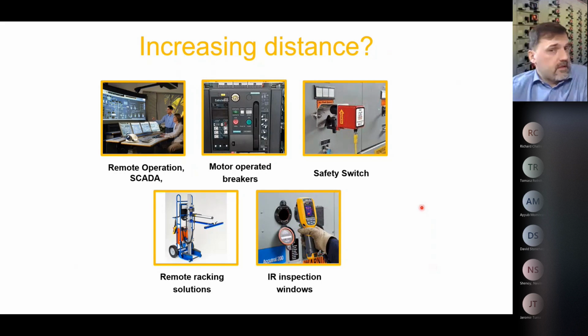We might increase distance. This will be under engineering controls if we look at the hierarchy of controls, but I think this is easier to understand this way. If you have your panel and your system, it might be operated by a SCADA system, which is remote operation. You are just sitting in the control office when you switch things. You might have motor operated breakers when you operate the system remotely. Only you have to remember that it's pointless to have a motor operated breaker when you are standing in front of it and operate it from the front panel of this breaker. Then you have some kind of control tablet or control screen when you are somewhere in the substation, but let's say a few meters away.